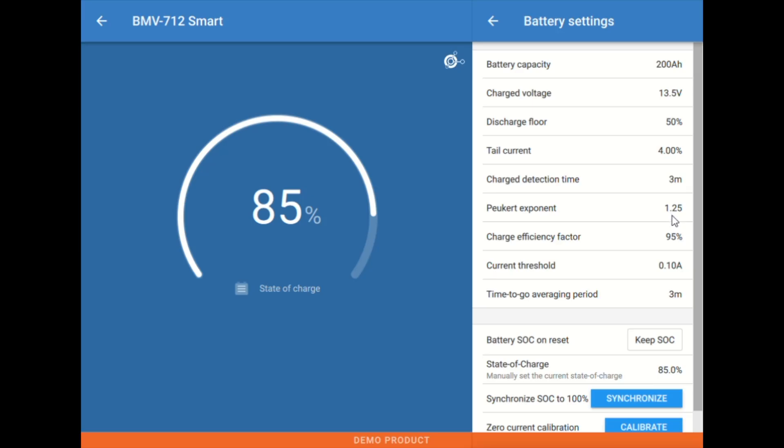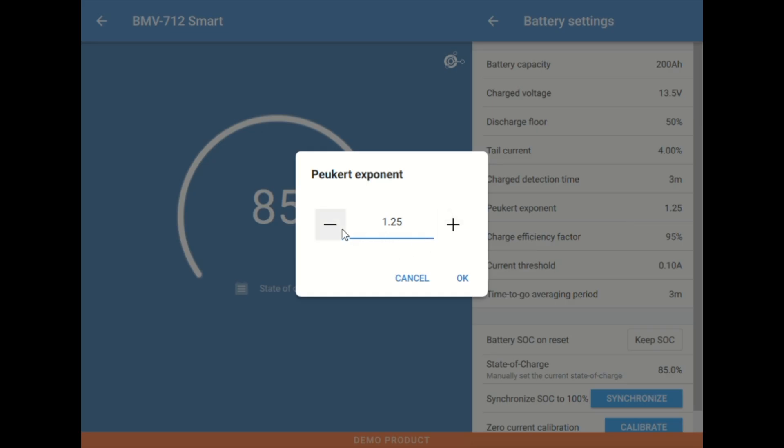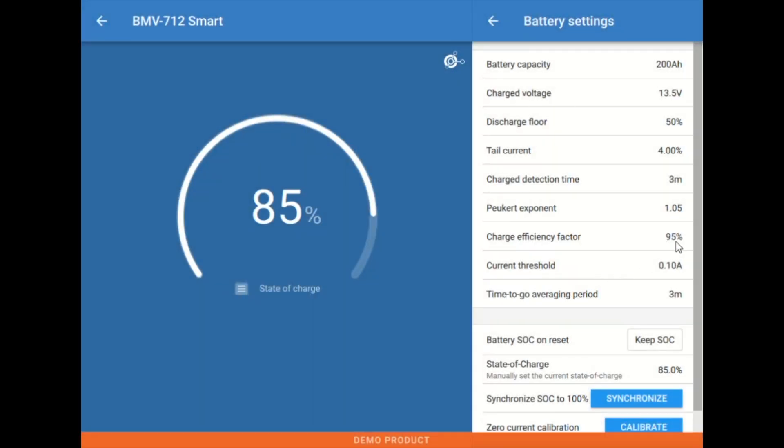You might go down to 1.20 if this is maybe a high efficiency gel or AGM. Or we would set this to 1.05 if this is a lithium battery application. So typically we're at 1.25 or 1.05 for lithium.